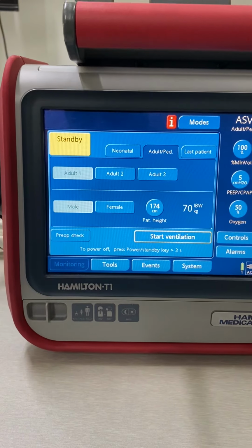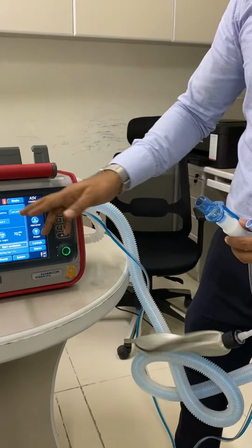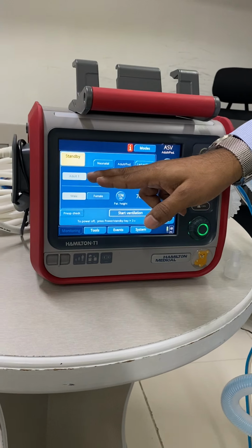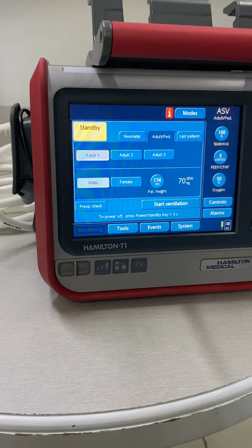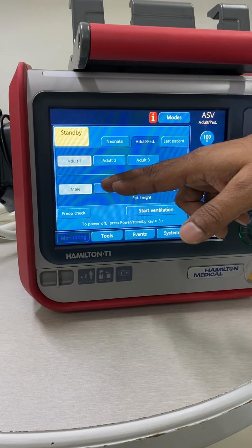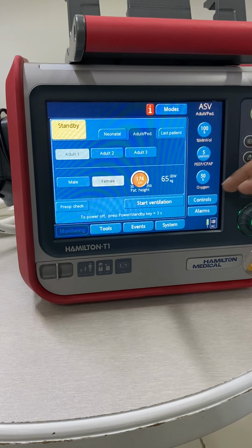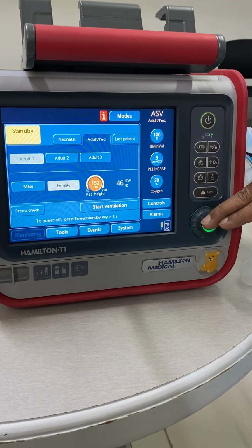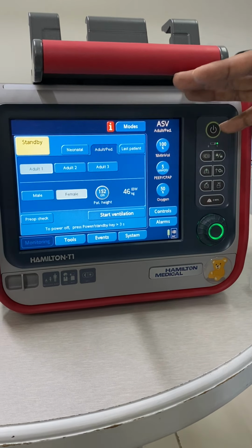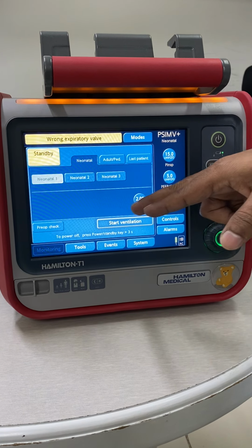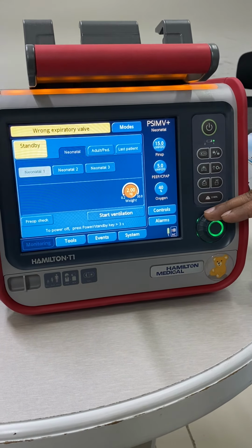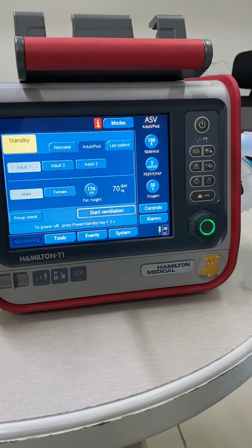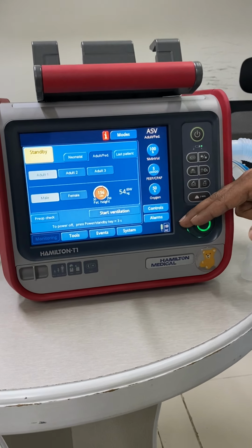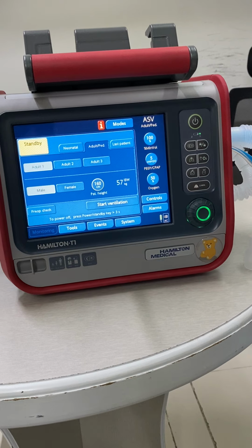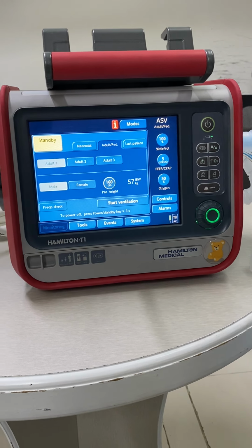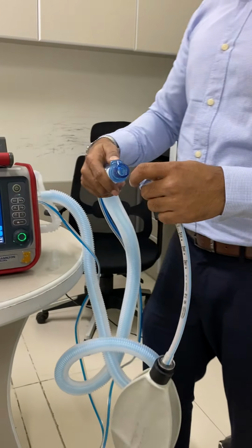So close it. Now to set up. How to set up the machine: now I'm choosing the pediatric adult group. You can see here adult 1, adult 2, adult 3. These are the pre-programs. If you want to program some mode and save it, you can use this one. But you can also choose the patient type, male or female, and enter the height of the patient. If you enter the height, it will give you the ideal body weight or expected body weight, and accordingly the default settings will come. If you choose the neonatal patient group, instead of the height, it is the weight. So you can enter the weight of the patient. We will go with adult pediatric and choose the height. It doesn't matter if you don't choose the height, you can always adjust the parameters, but it will give you an idea of how to set up default values according to the weight. Okay, now connect the patient.